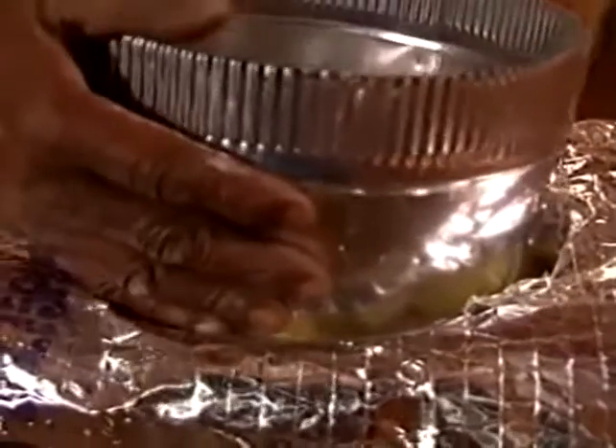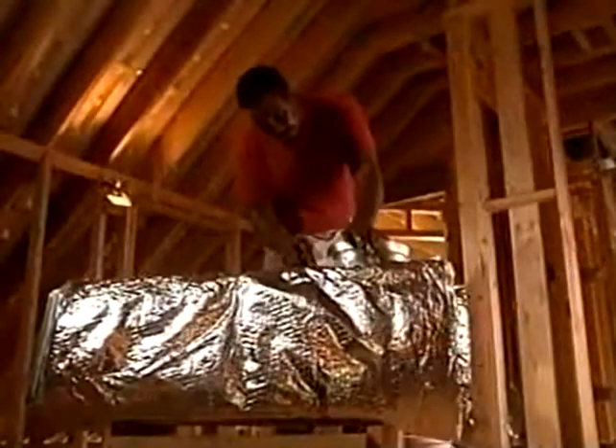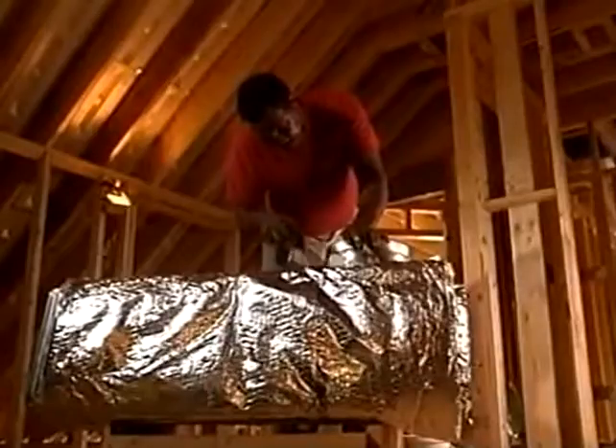Air leakage is most likely to occur where two components of the ductwork are attached. Let's take a collar, for example. When attaching a collar to a metal box, it's standard practice to join the two pieces by depressing the metal tabs on the bottom of the collar to hold it into place. However, without proper sealing, this can be a major source of air leakage. This contractor first seals the outside of the collar with mastic, careful to cover every possible gap. Then he reaches inside the box and paints mastic over the metal tabs underneath the collar. Notice how he covers the entire surface. This is a good example of how this connection should be sealed. Remember, every joint can be the source of air leaks.